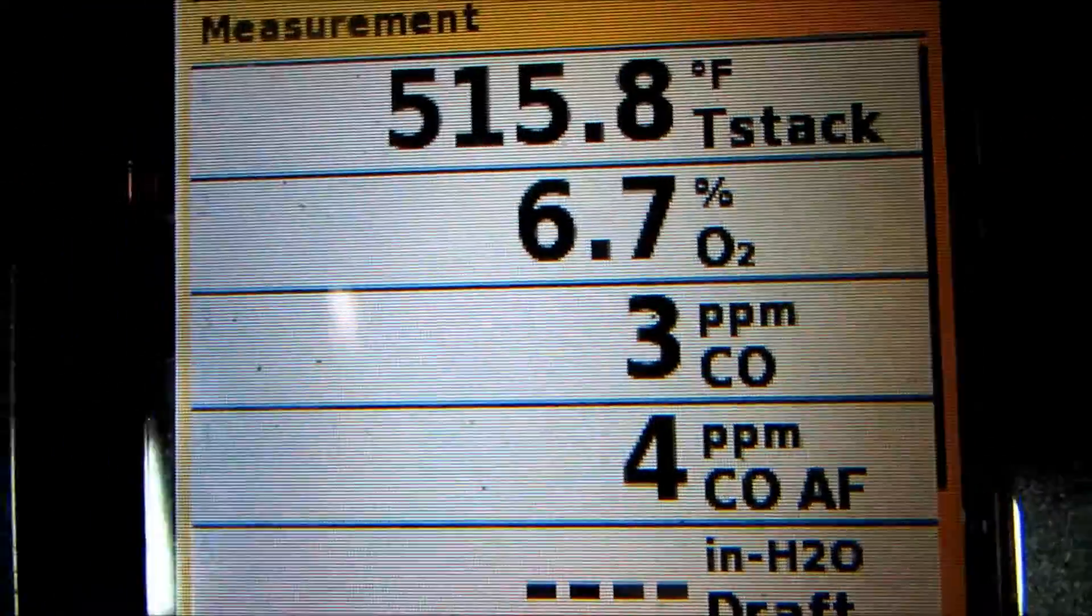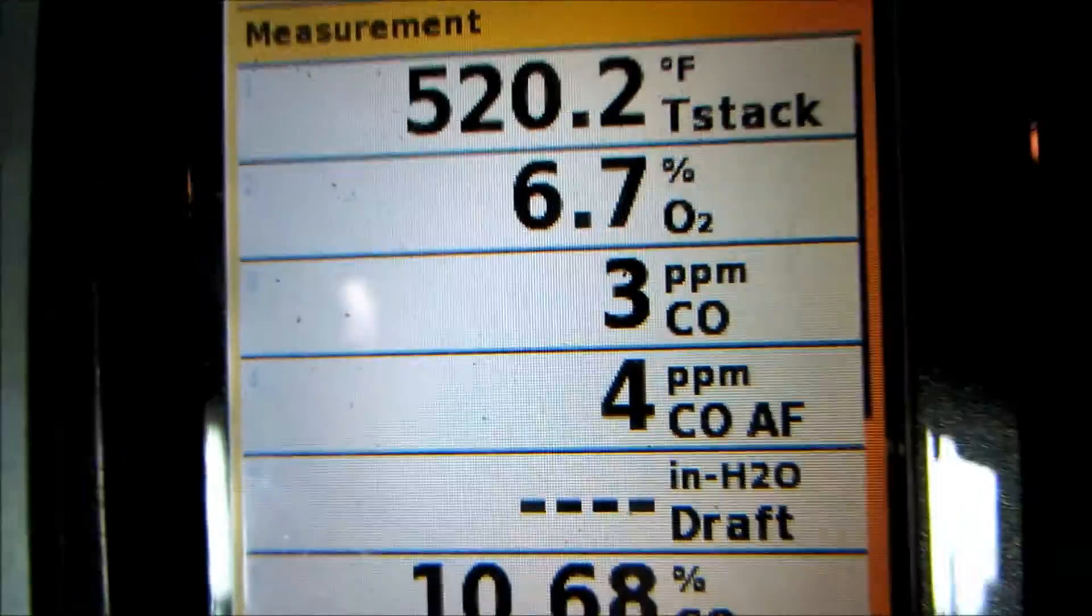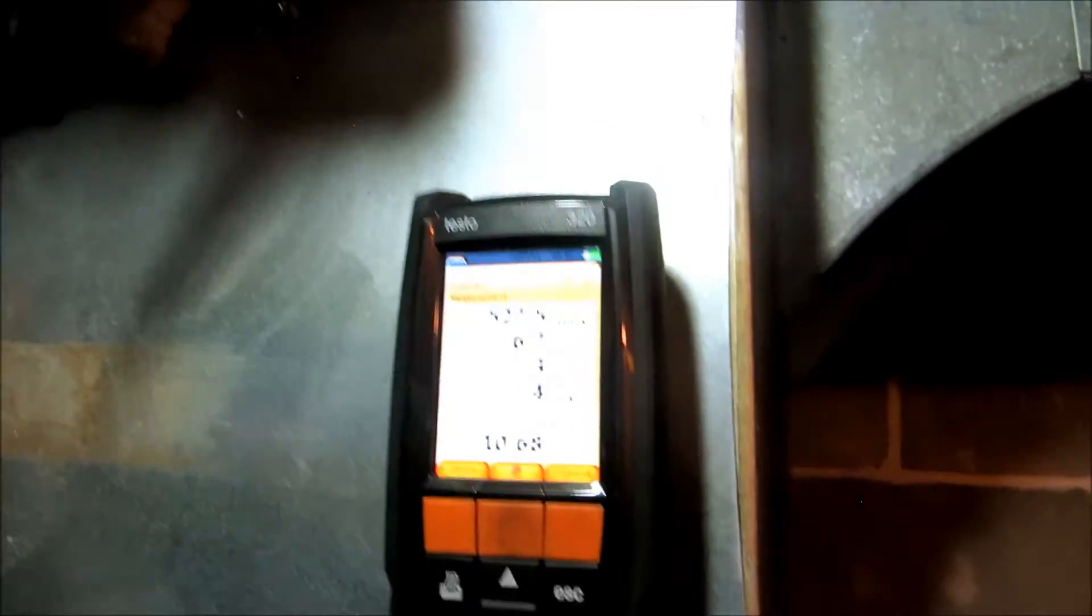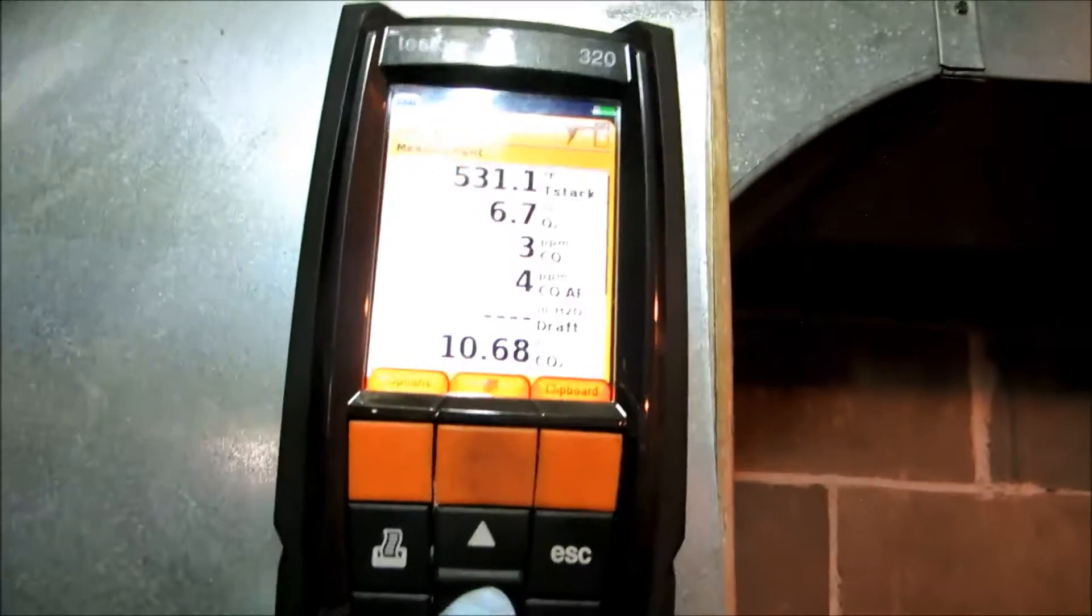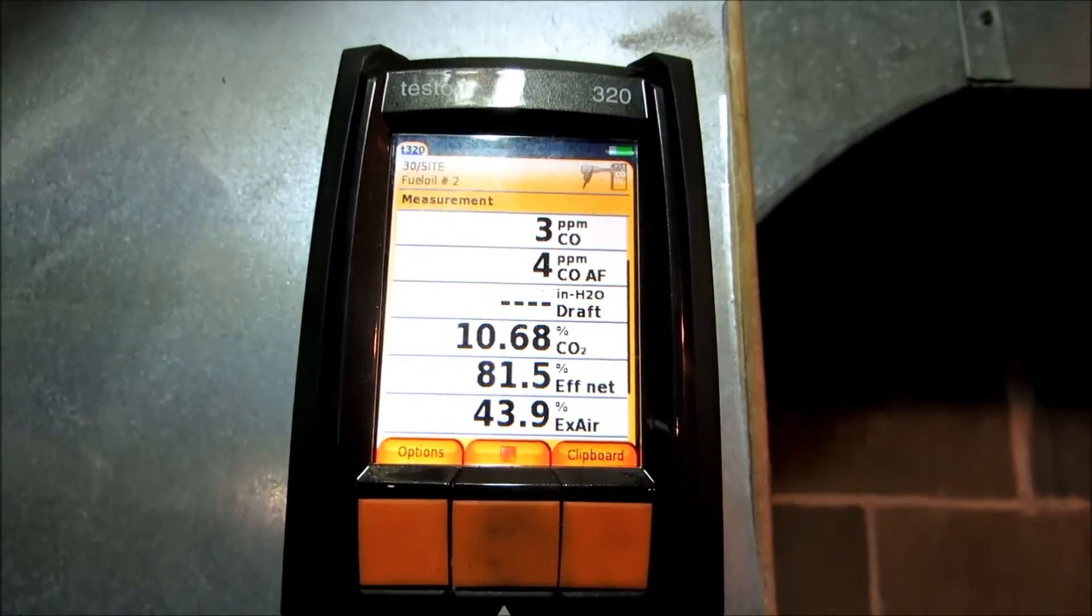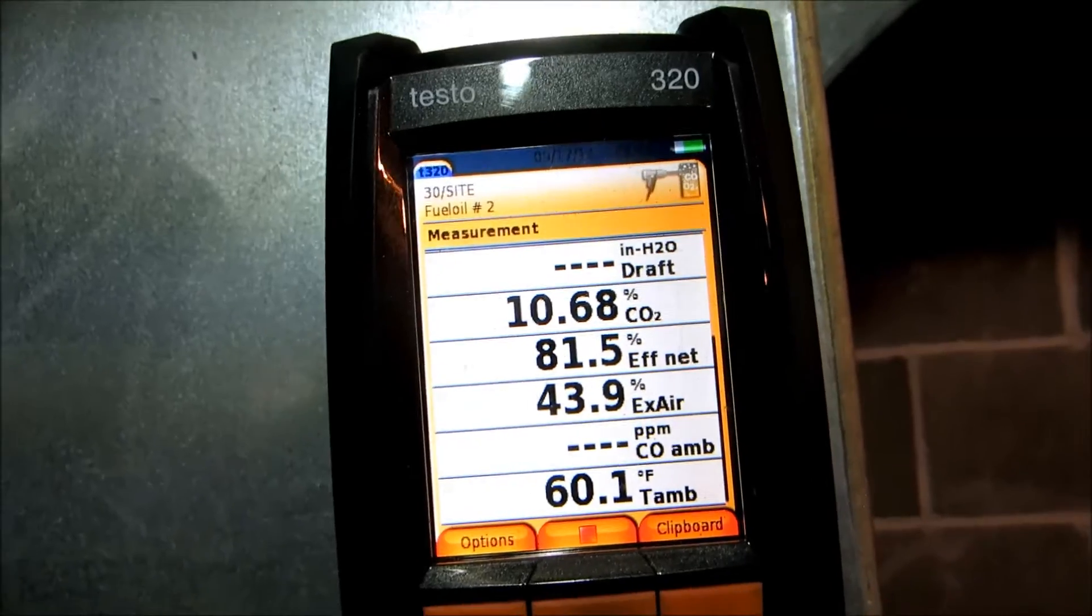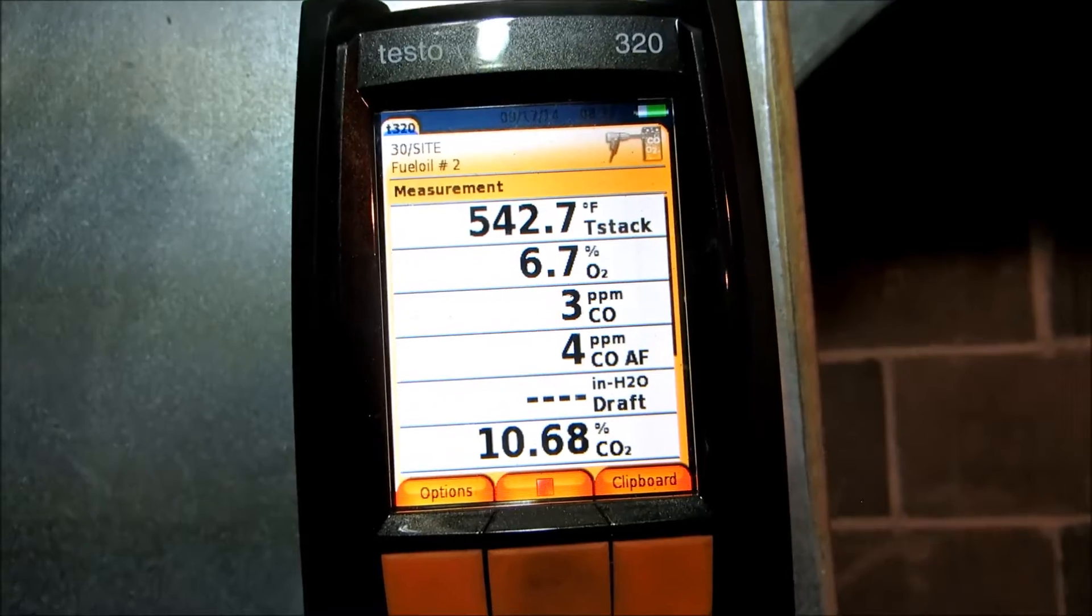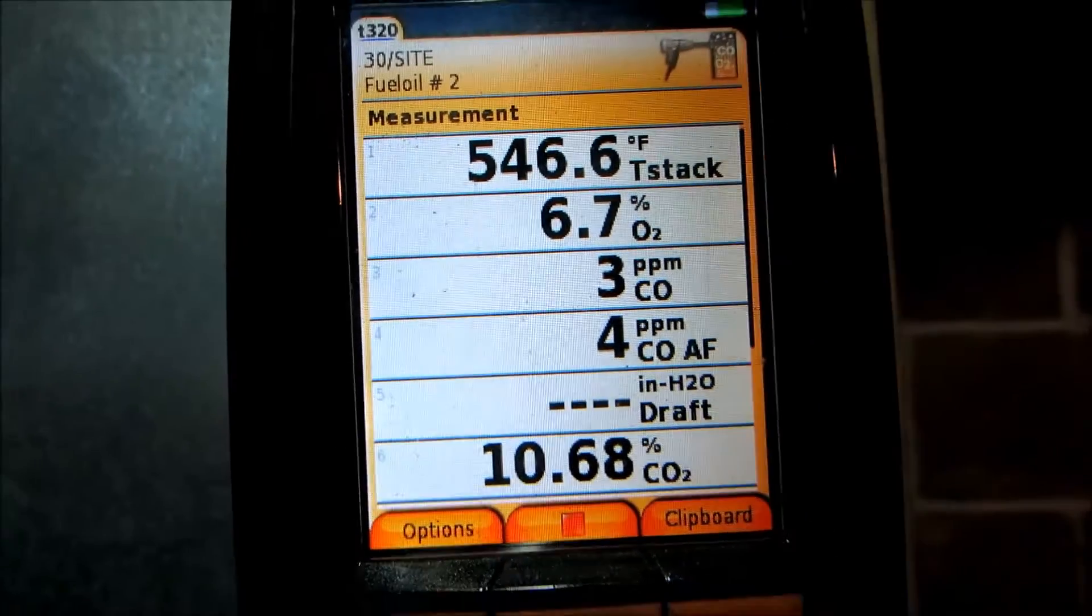See, 10 and a half on the CO2. I could give it less air but I'm probably going to leave it there. Incomplete combustion would be high carbon monoxide parts per million, so that's pretty complete right there. It's a little bit leaner than I like, but I'd rather run it lean.